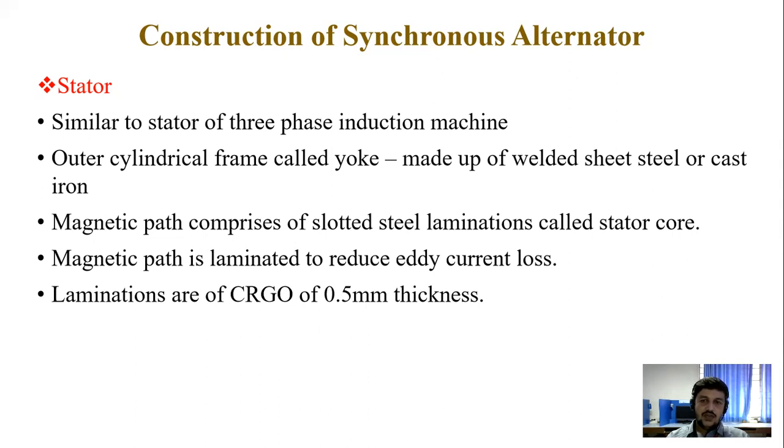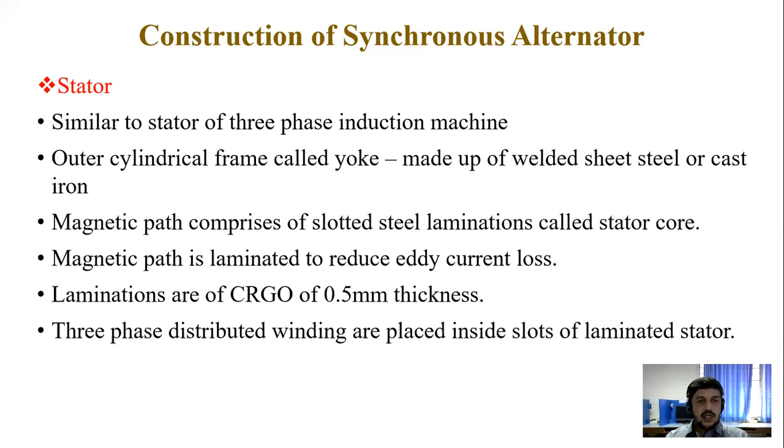That will increase the effective resistance of the entire stator core, and that will reduce the flow of eddy current inside the stator core. Ultimately, that will decrease the power loss due to eddy current. Now, whatever three-phase distributed winding is there, that three-phase distributed winding is placed inside the slots of the laminated core.